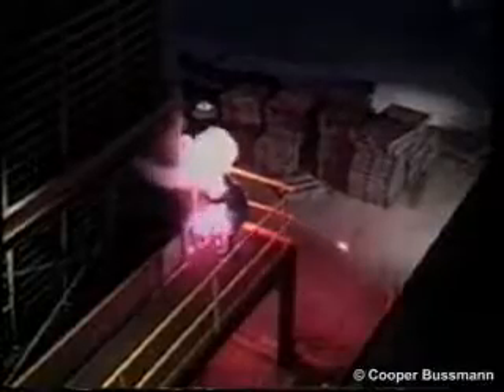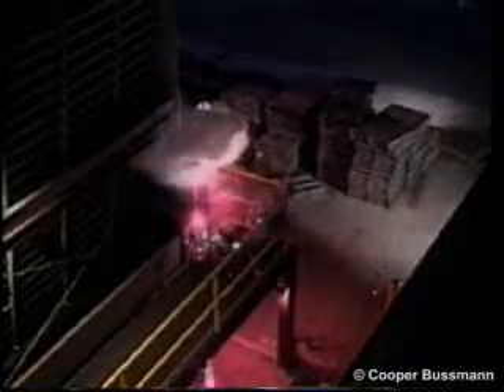An arc blast is the force caused by the rapid expansion of air and the transition of solid conducting materials into vapor. This expansion of solid material to liquid and then into a conducting gas is significant and potentially very dangerous. When an arc flash occurs, copper conductors, contactors, and terminals can vaporize. This vapor can occupy more than 67,000 times its original volume.